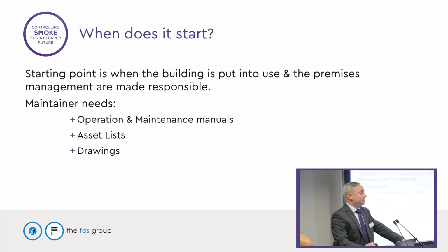Drawings of where are these devices? How many floors? What are the cable routes? Logbook. We need a logbook because apparently you're supposed to record all your weekly testing, monthly testing, and all your faults into the logbook. So if that's not happening, you've got no record of evidence should somebody come in to audit you. And by that, I mean the authorities.